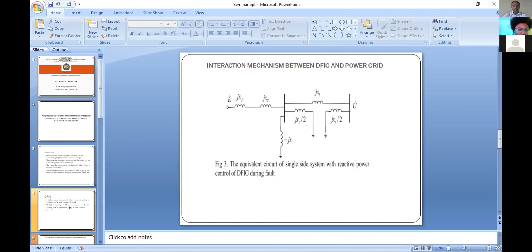How does the control strategy of a DFIG influence the transient stability of a power system? The reactive power control strategy during a fault will influence the transient stability in a way that the power curve will be stretched by increasing the reactive power during the fault. The more the reactive power, the more it will be stretched, so the acceleration area will then reduce. This is very favorable for the transient power angle stability of the power system.